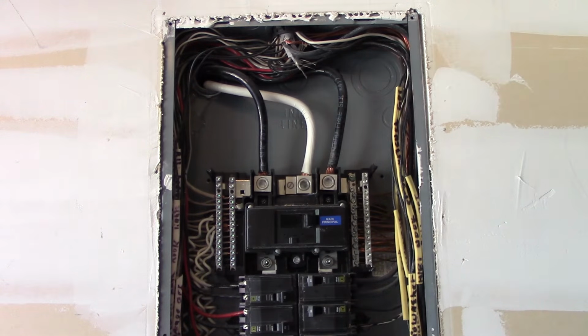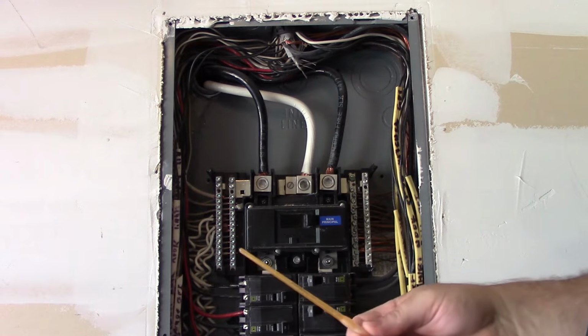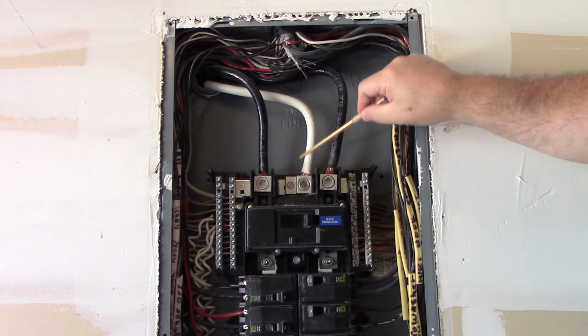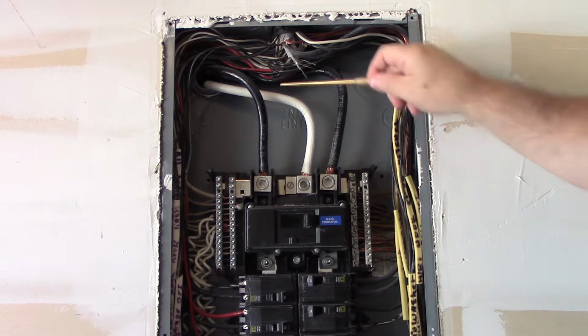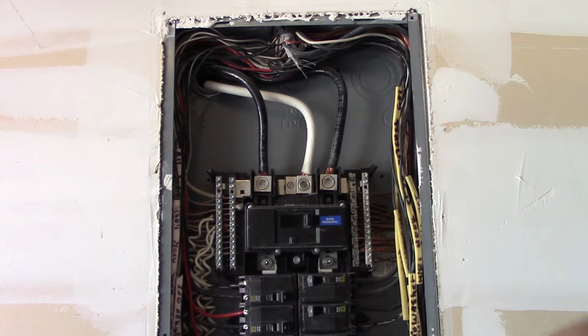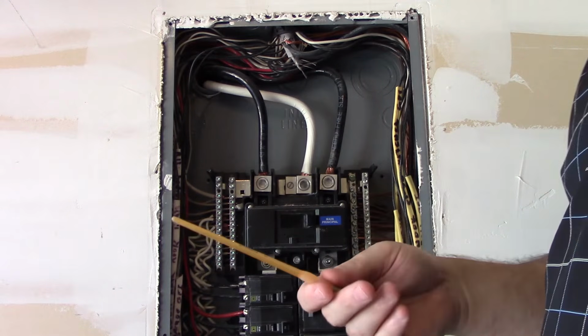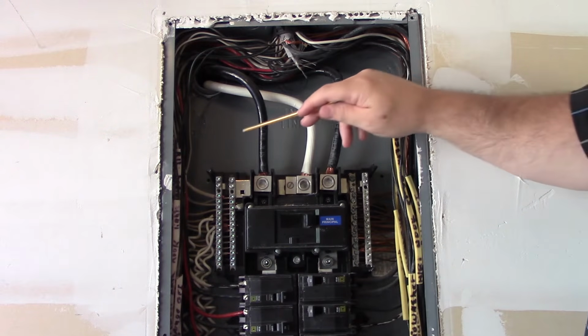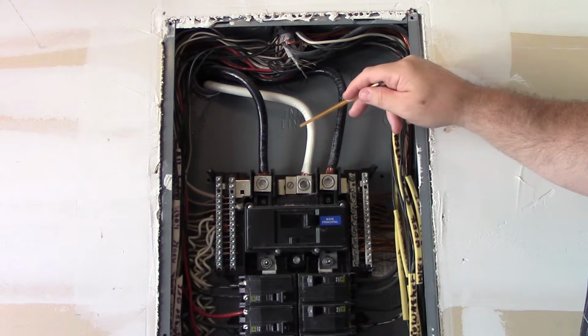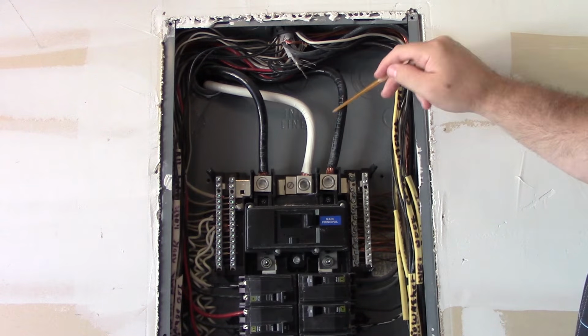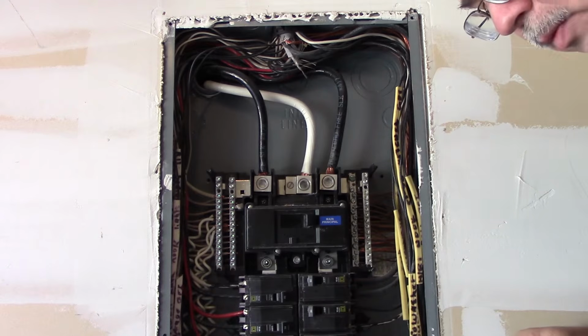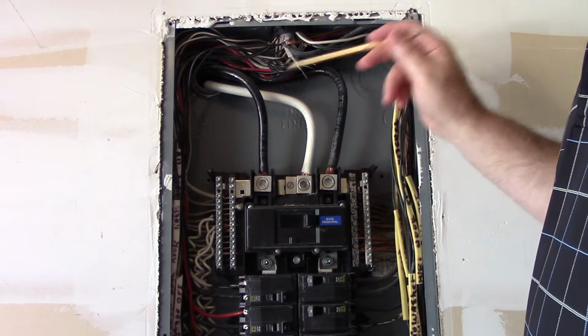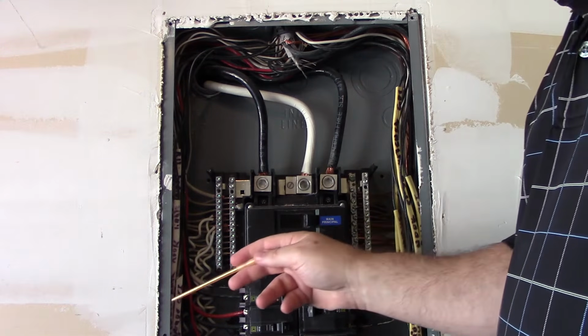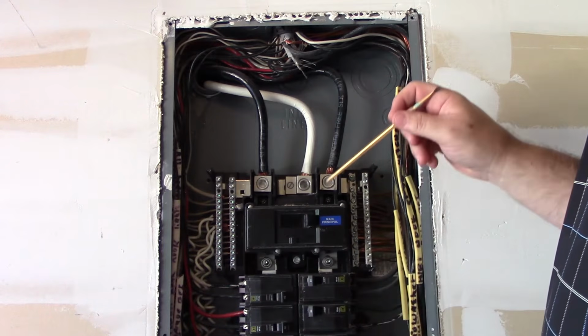And as we said earlier, these are your ungrounded conductors, or referred to as a hot. And this is your neutral or grounded conductor. Now, in a 120/240 volt application for a one family dwelling like we're dealing with here, a single family dwelling, or 1 and 2 family dwellings, then this is a 120/240 volt application. Then what we're going to notice is we've got only 3 conductors coming in. So that tells us that we have a 120/240 volt application. Also, we'll find that on this legend over here in a little bit as well.